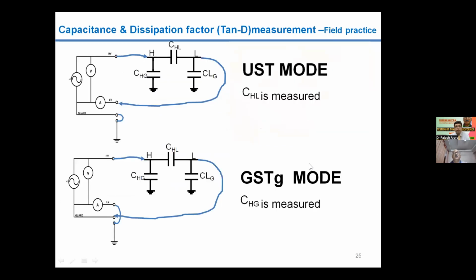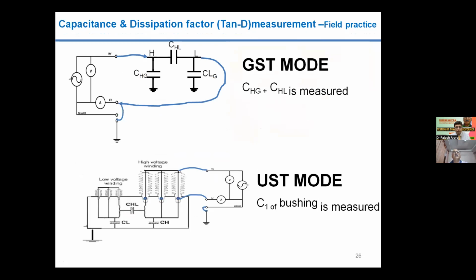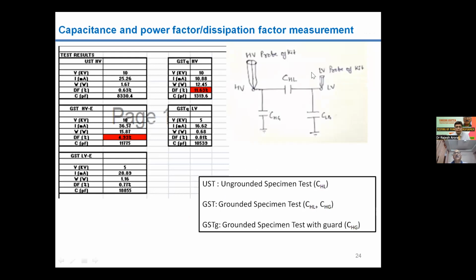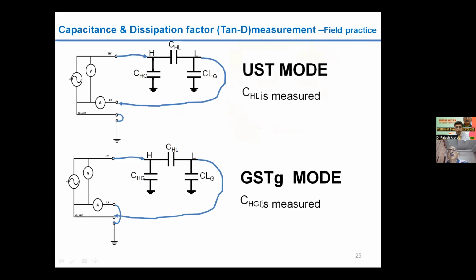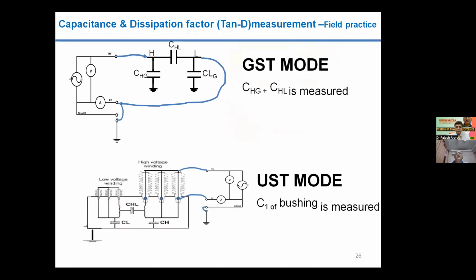Okay, next. So these are the principal diagrams showing how we test the different tan delta values and how these values are calculated. The diagrams show how these different tests are done, but the arrangements are inside the kits themselves. Generally, we connect once, and all the correct connections are made automatically by the kit. In the figure, we connect the test high voltage probe on the HV winding, and the response is measured on the LV winding, and accordingly the connections are shifted inside the kit to measure various types of tan delta values.